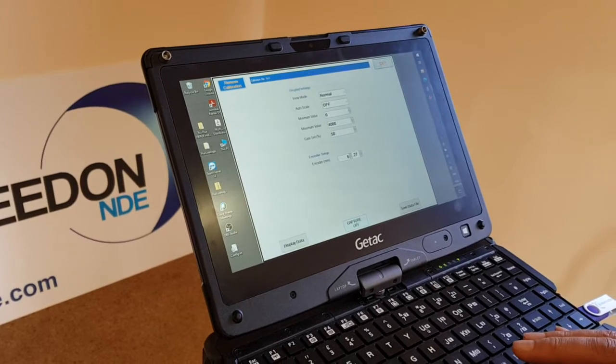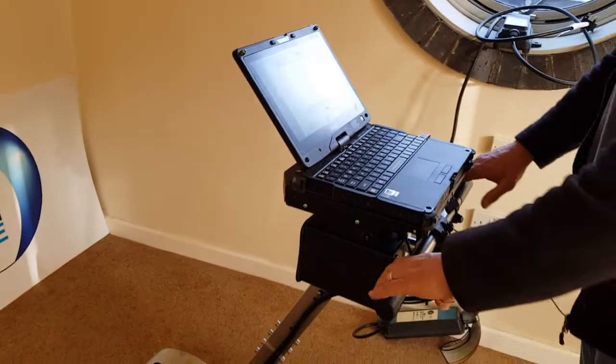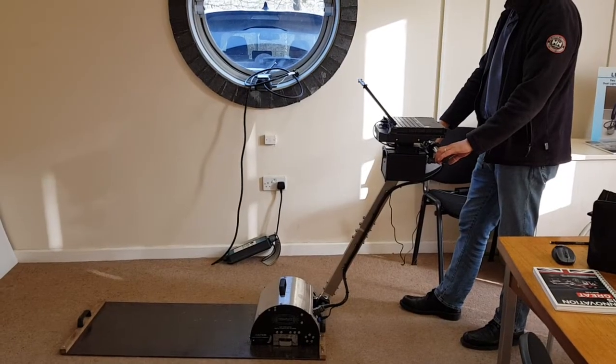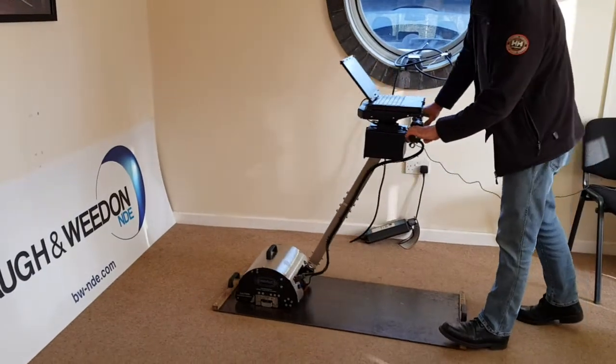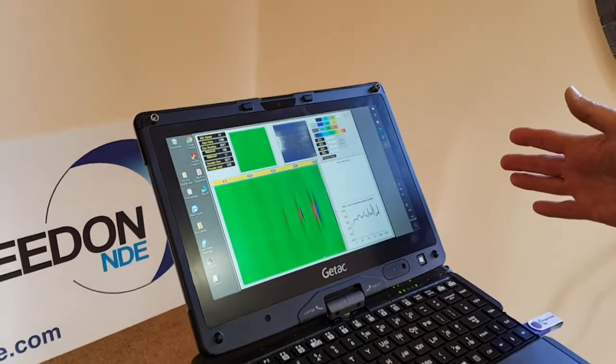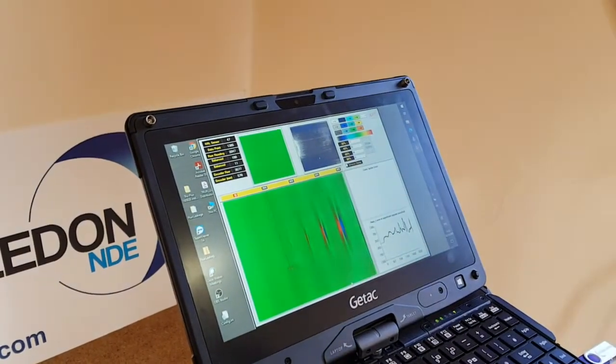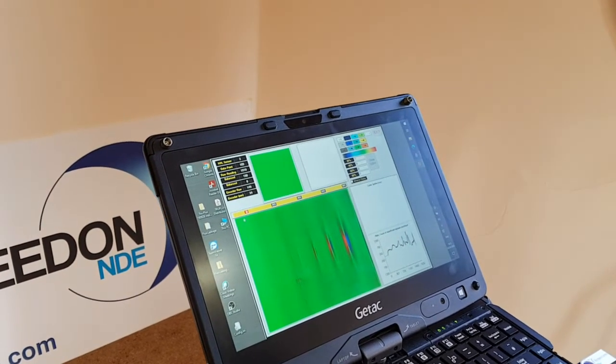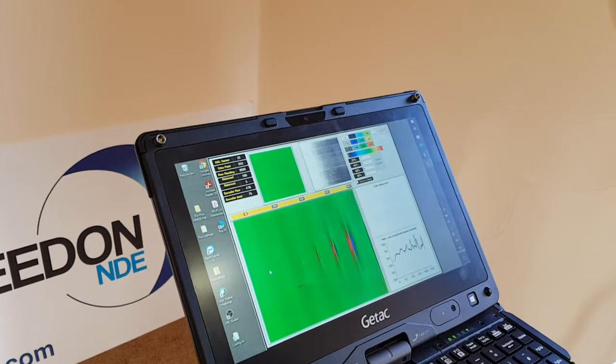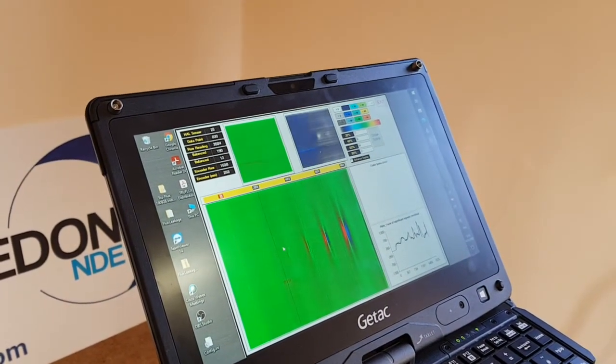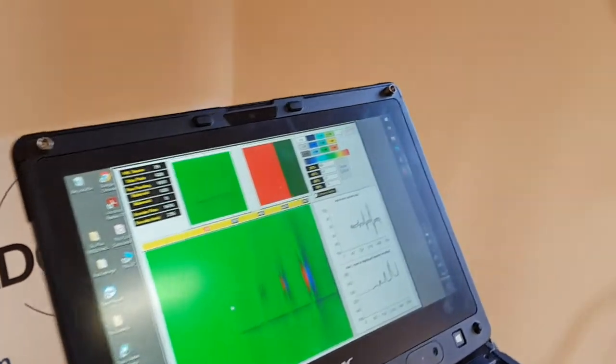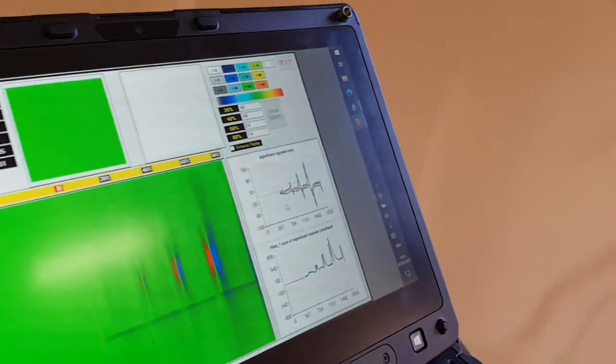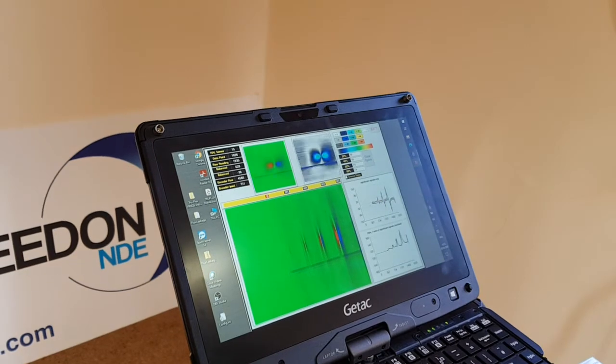I've got to the end of the calibration scan. I've turned capture off and I've got this display. First thing we do now is set the base level. The way we do that is move the cursor over to near the 20 percent indication. So if I move it here, select, I've now changed the base level. So now you can see the defects down here and up here.